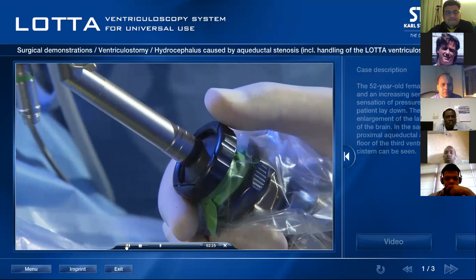Now, we have color coded the endoscope. The green color over here marks 0 degree. Why it is important for paramedical staff and doctors to know these color codes which have been standardized? Because in any endoscopic procedure, the surgeon prefers to have very less light in the OT. So the top lights are usually dimmed off so that the monitor can give you a sharper image, and a green color refers to the 0 degree.